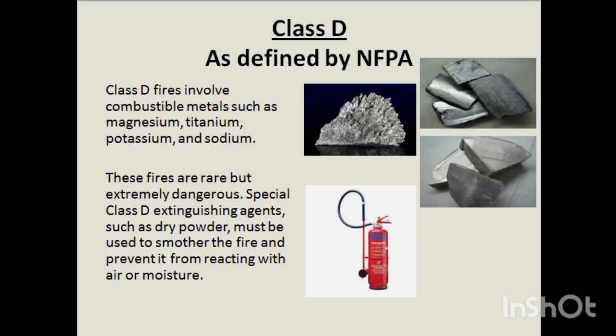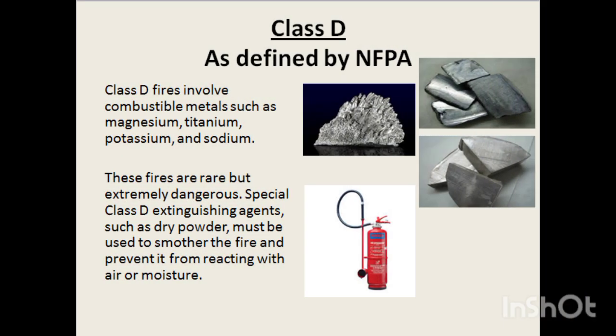Class D fires involve combustible metals such as magnesium, titanium, potassium, and sodium. These fires are rare but extremely dangerous. Special Class D extinguishing agents, such as dry powder, must be used to smother the fire and prevent it from reacting with air or moisture.